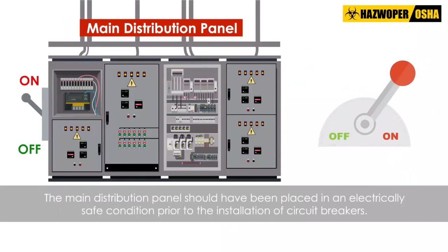The apparent justifications for failing to de-energize electrical equipment in this incident, which focused solely on the inconvenience of shutting power off, do not meet the necessary conditions for working on or near energized electrical components under NFPA 70E.